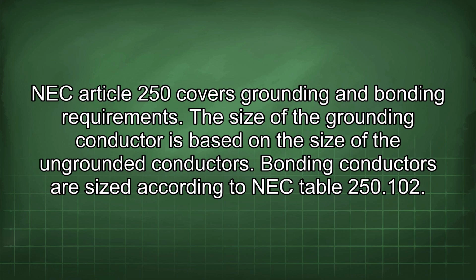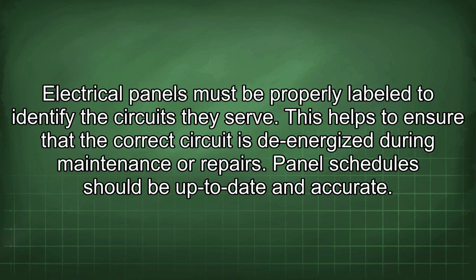The size of the grounding conductor is based on the size of the ungrounded conductors. Bonding conductors are sized according to NEC Table 250.102. Electrical panels must be properly labeled to identify the circuits they serve. This helps to ensure that the correct circuit is de-energized during maintenance or repairs. Panel schedules should be up to date and accurate.